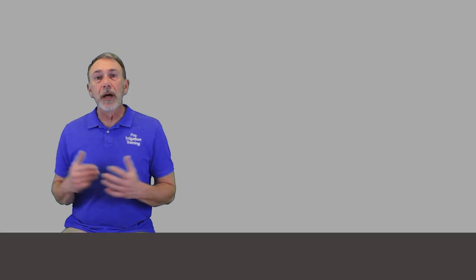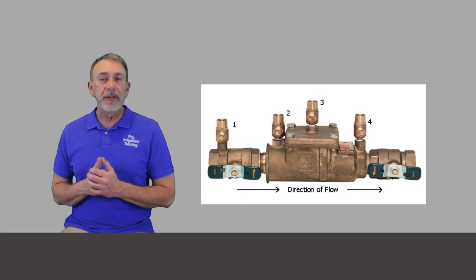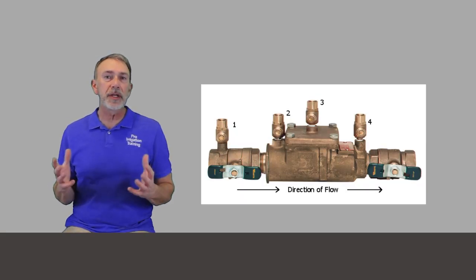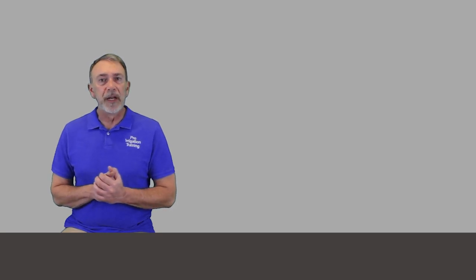And so now we have the double check valve assembly, and this is probably what's most ubiquitous or what you're going to see the most in the irrigation business, either the anti-siphon valves or the double check valve assembly. And this one doesn't have to be mounted above or below anything. It can be underground in a pit, in a box. It needs 12 inches clearance on all sides but it doesn't need a drain or anything like other ones do.